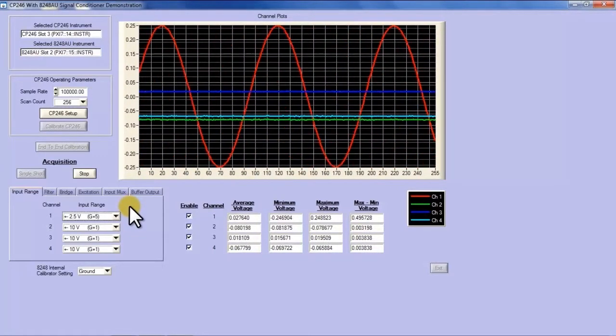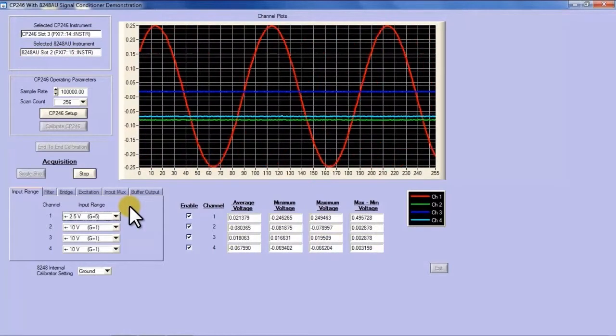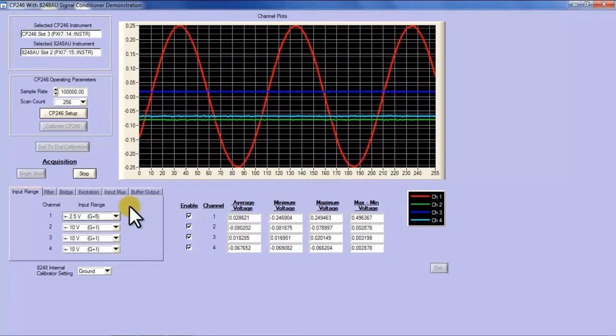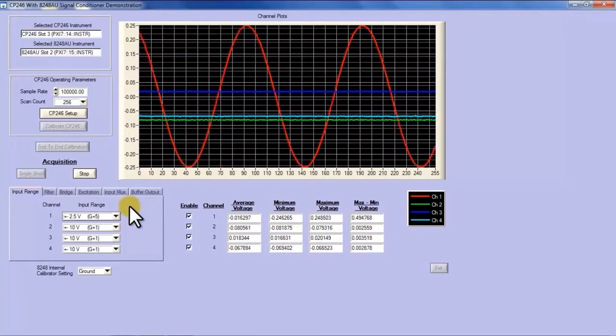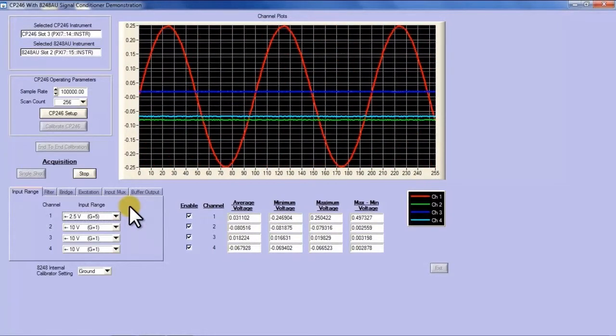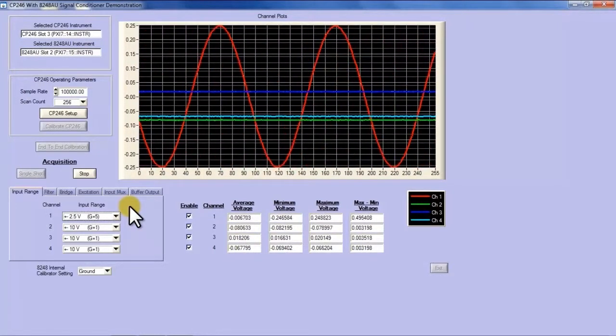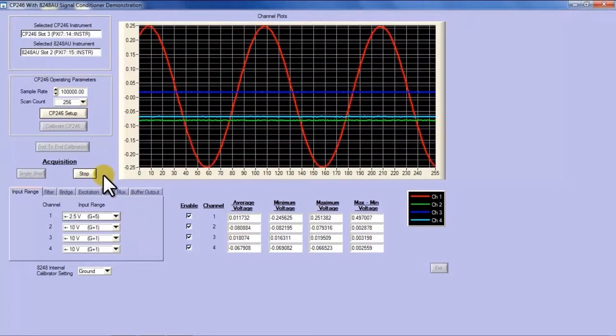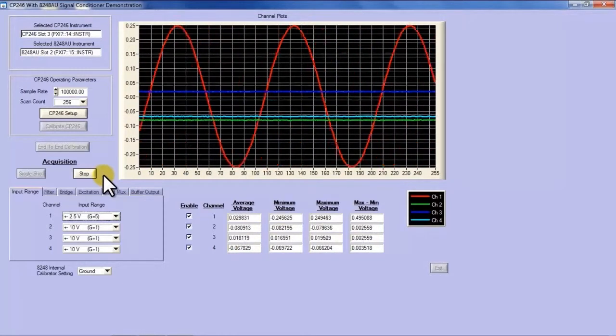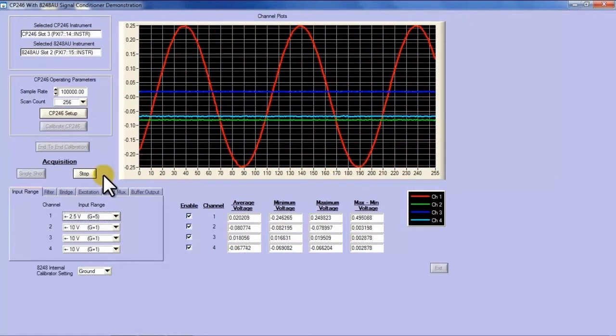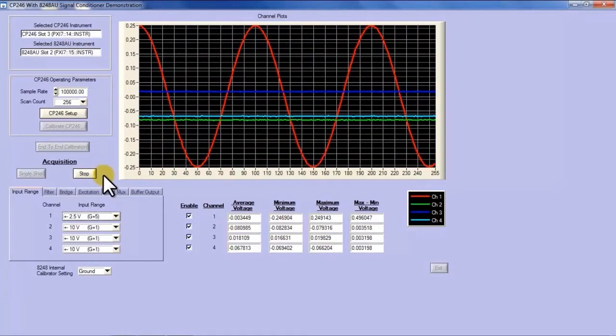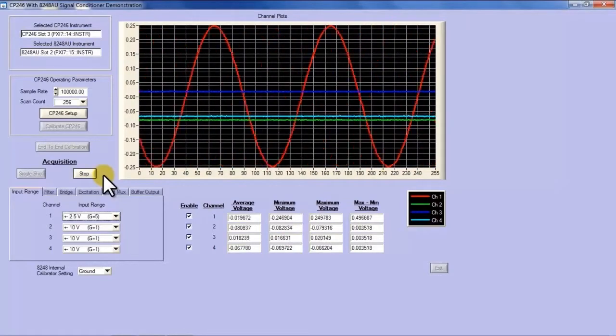That can be a complicated procedure with two kinds of instruments, especially a signal conditioner which has its own transfer function and an A to D converter that has a separate transfer function. The 8248 has an onboard precision calibrator that allows you to inject a signal into each channel, digitize that, and get the transfer function of the entire system.